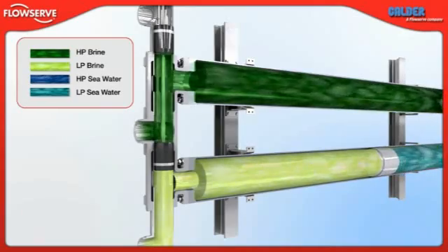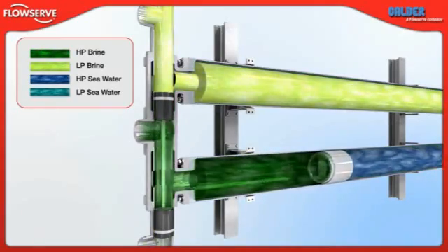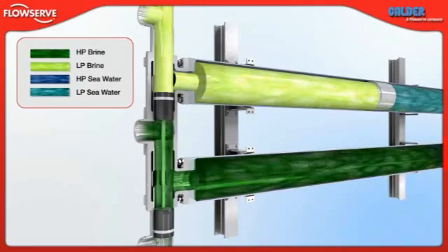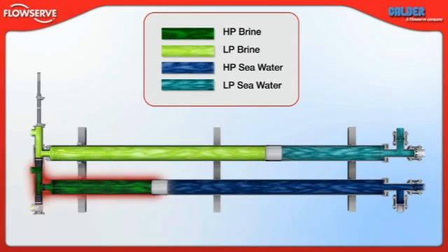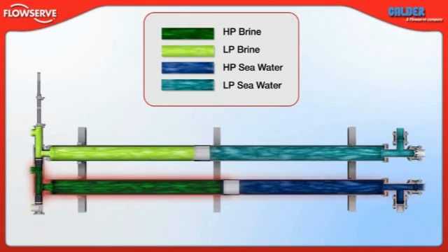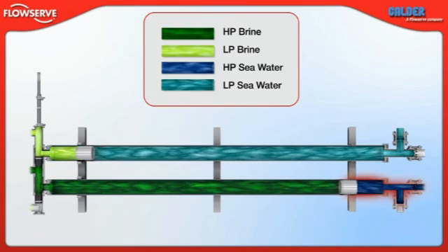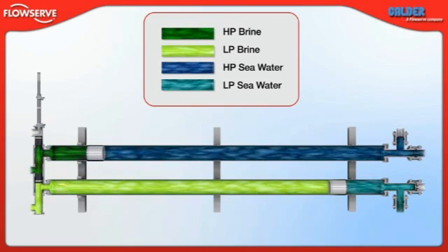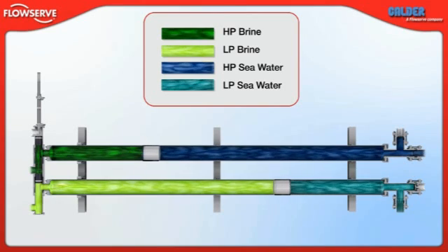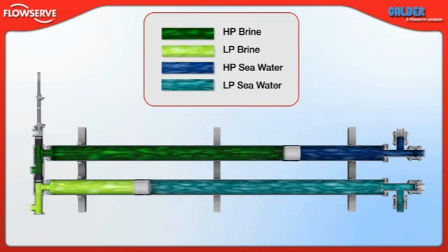At this point, the LinX valve actuates and the process repeats itself but in the opposite vessels. As high pressure brine enters the LinX valve, it is directed into vessel two, where it pressurizes the sea water introduced during the previous half cycle. At the same time, in vessel one, low pressure sea water displaces the low pressure brine to discharge and the cycle repeats.